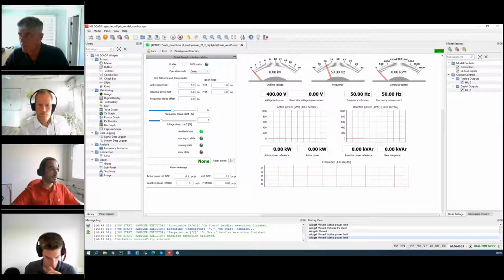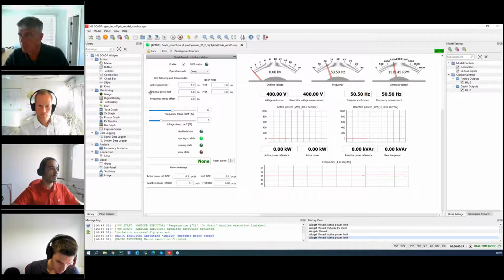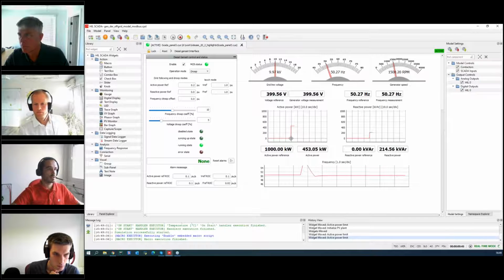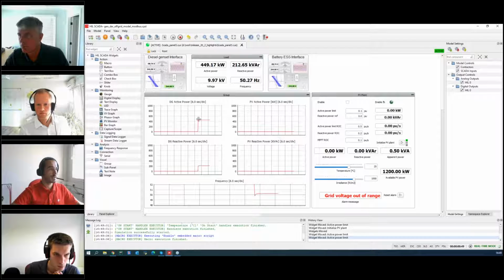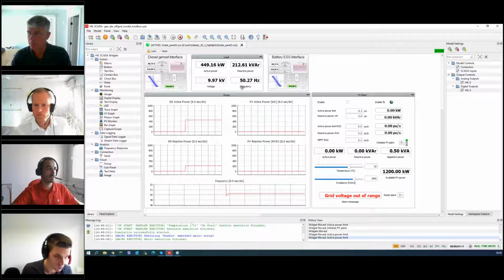So let's, for example, enable the diesel genset here in the droop mode of operation with an active power reference of 0.2 per unit, and here are the droop parameters. Now we can see that the diesel genset took over the load. Let's go here and see on these graphs. There was some frequency dynamics. Now, because the diesel genset is working in droop, we have a frequency that is close to 50 Hertz, but not exactly 50 because of the droop characteristics.